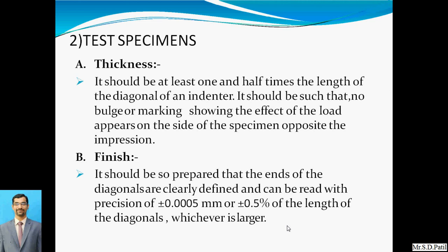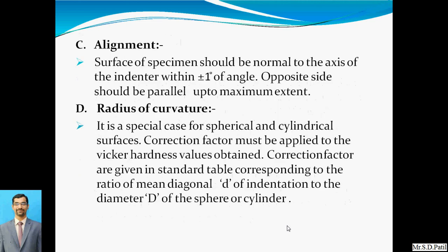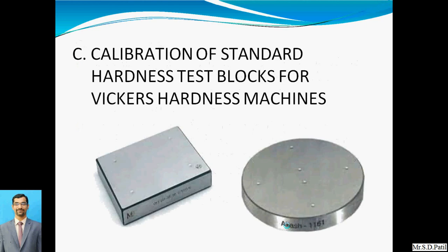Then whatever finishing is required for the surface, basically it will be a precision of plus or minus 0.0005 mm, or 0.5% of the length of the diagonal. Then alignment, that is the surface of the specimen should be normal to the axis of the indenter within plus or minus 1 degree of the angle. So this is all about the standards that we have to maintain while taking the test.